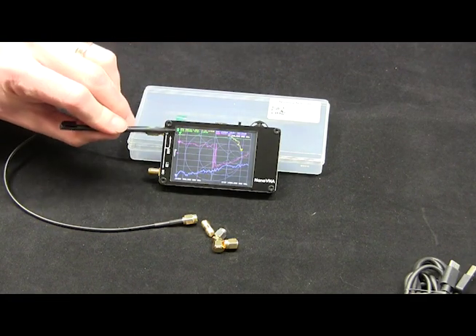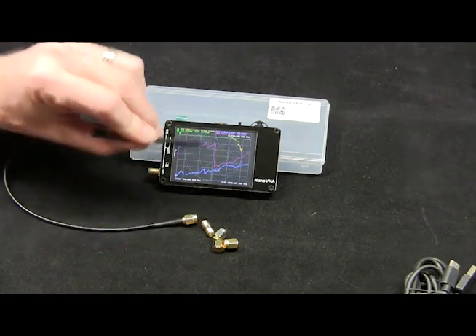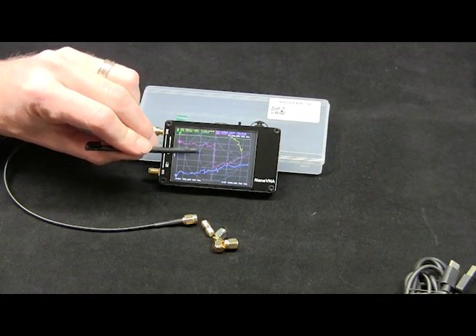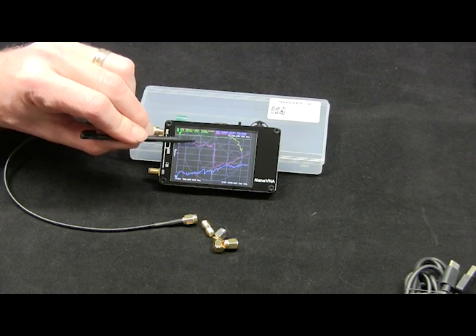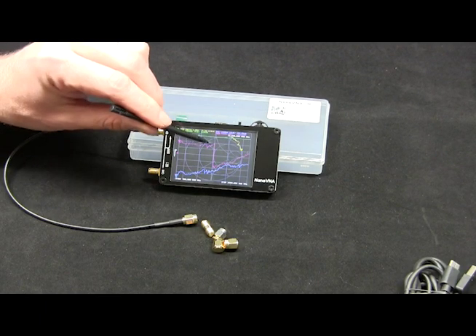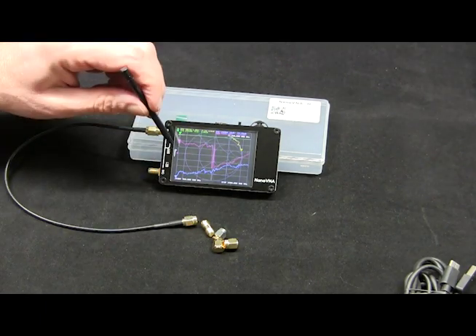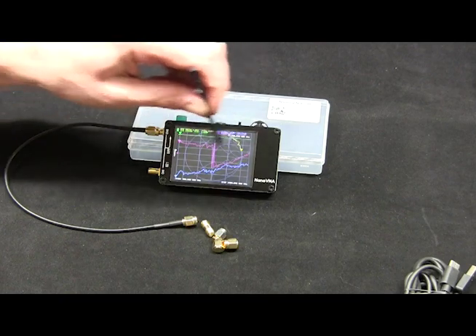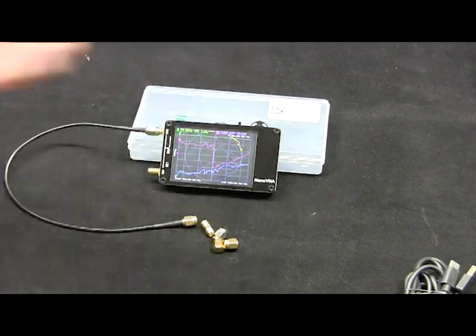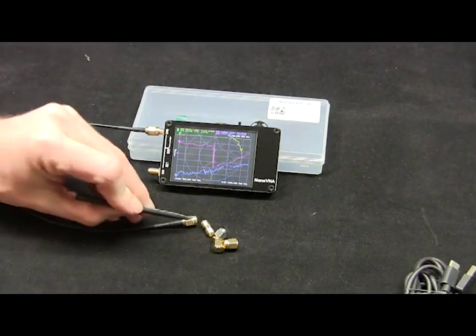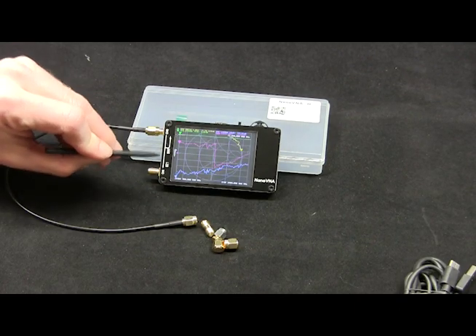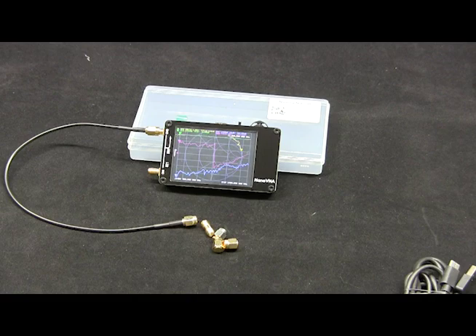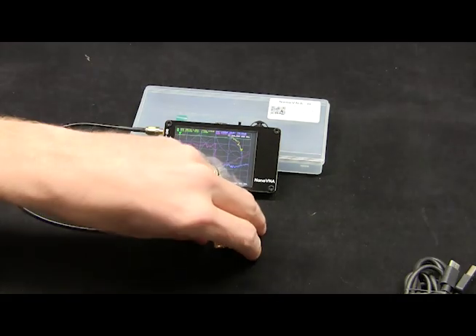We can also look at S11. When we have a load attached, S11 should be low. We measured minus 25 dB. And when we put an open or a short on this, it should either be here or here. This is for a short, this is for an open. And finally, when we connect the cable to here, you should see that the S21 goes to 0 dB, meaning there's no loss.